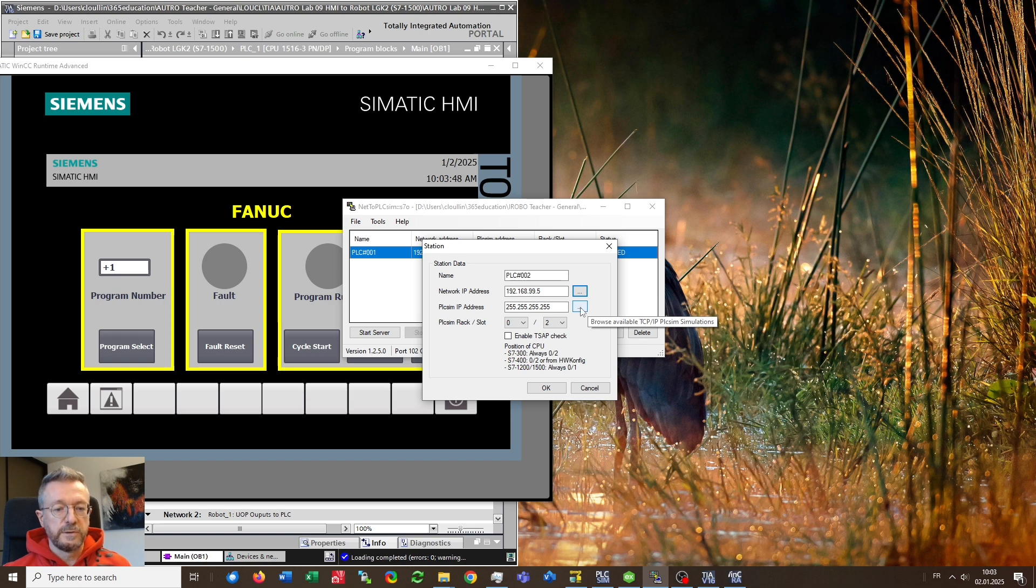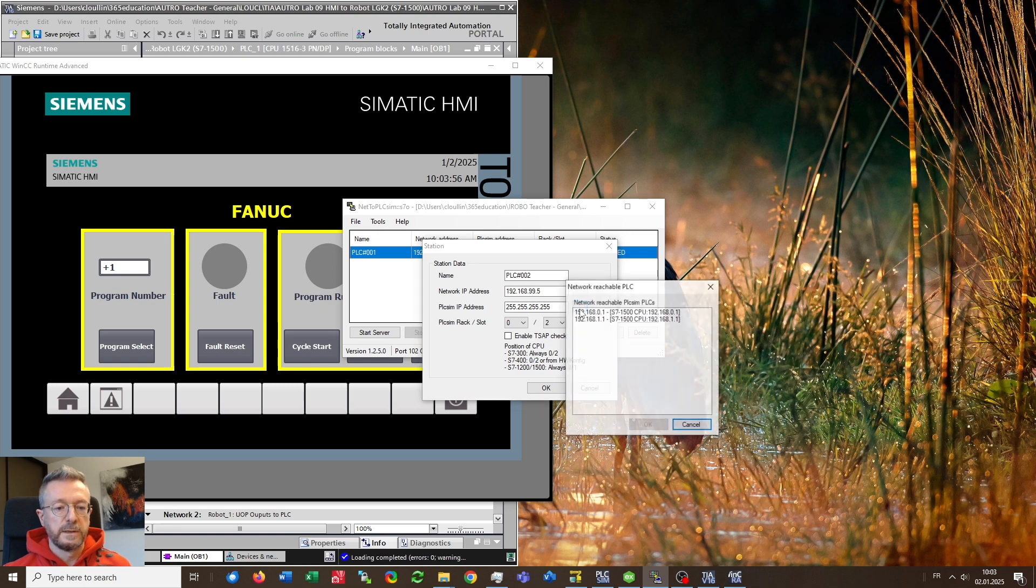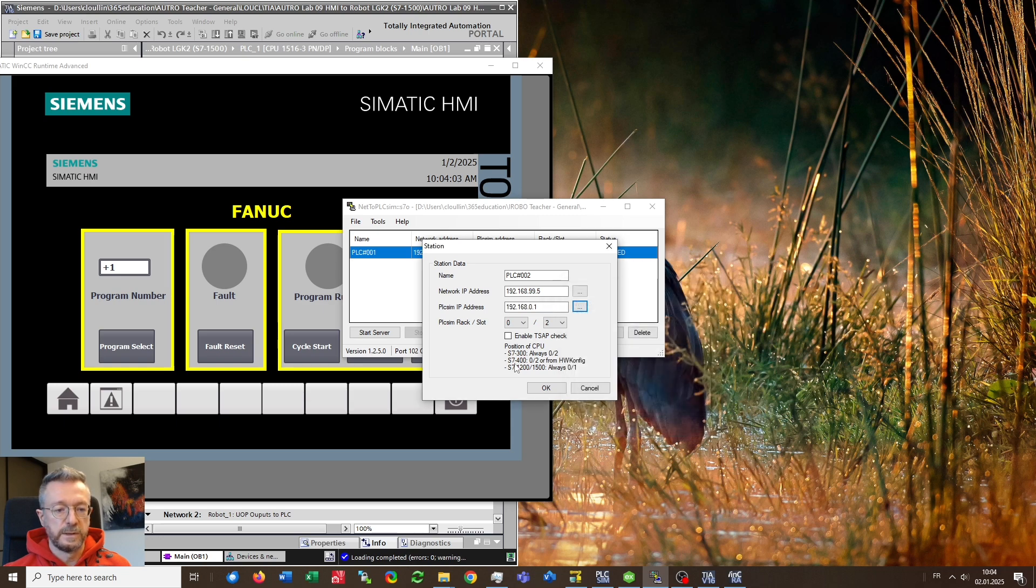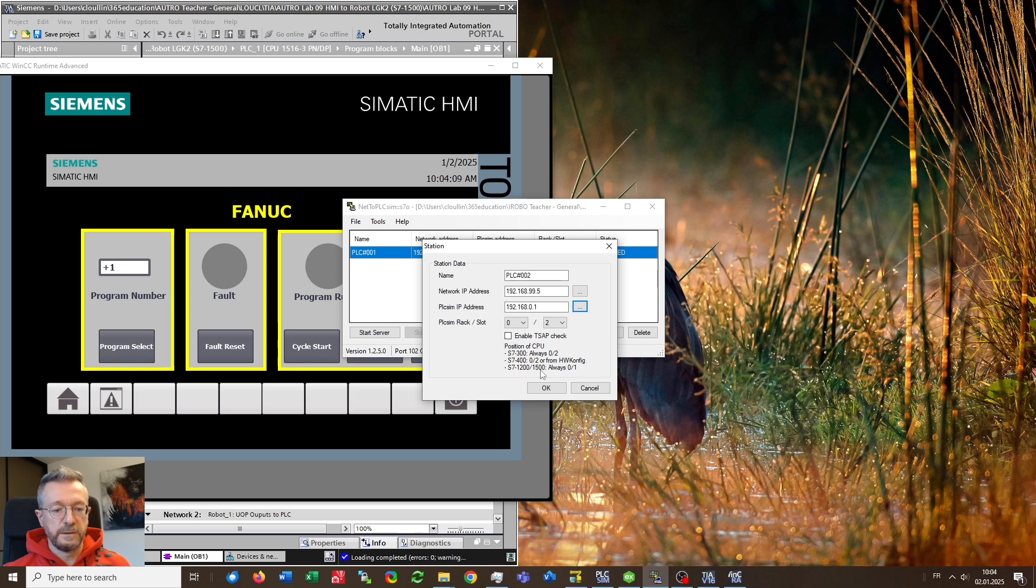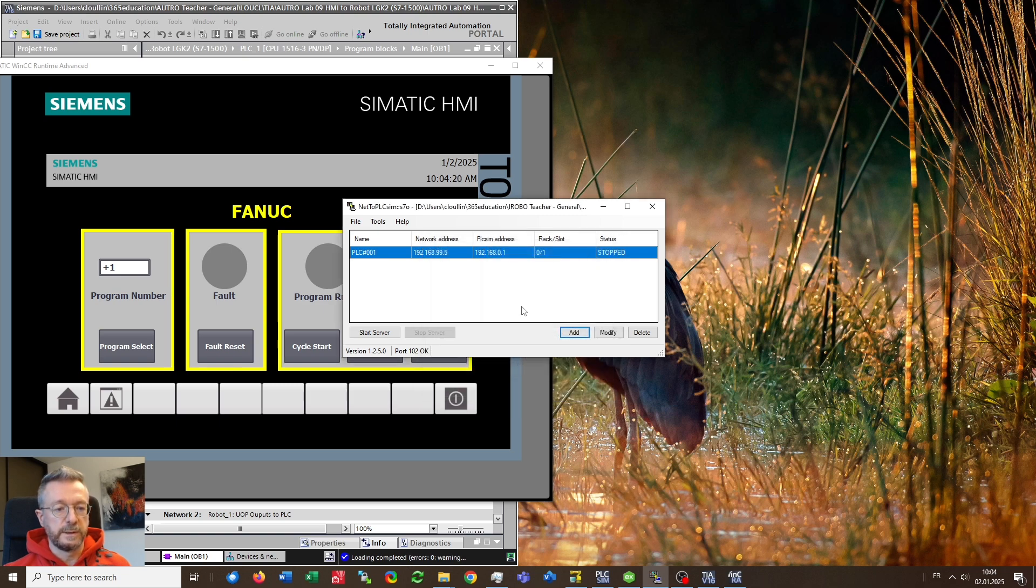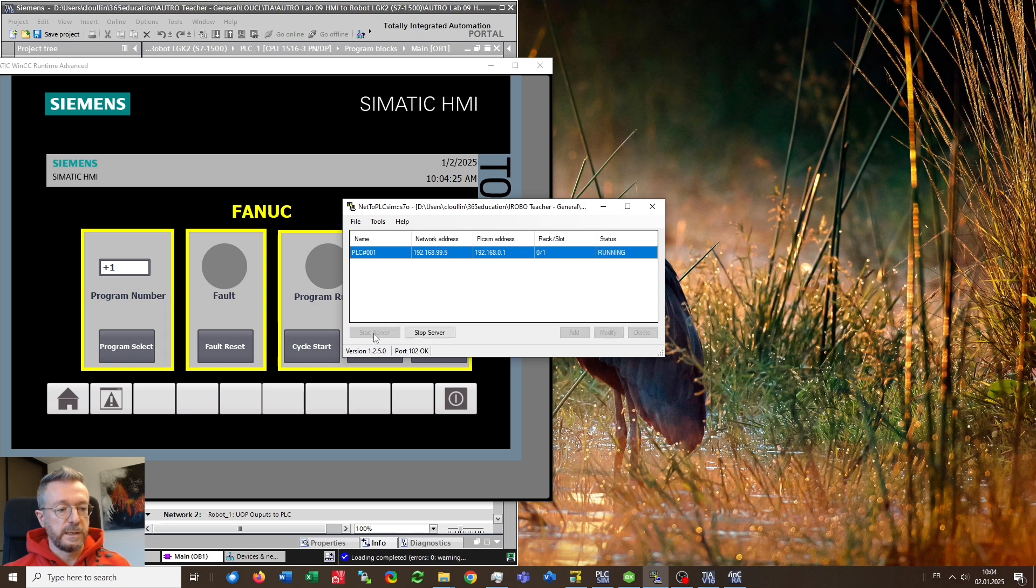Second IP address is the real IP address of your PLC that you have foreseen in the TIA portal. So if PLC SIM is running already you will see them here and you can select the one that will work for you. As I'm using an S7 1500 it suggests here to choose a rack and slot 0 1 so I will do this too and you would click OK. I will click cancel as it's already done so all this corresponds to this line then you start don't forget to start the server.